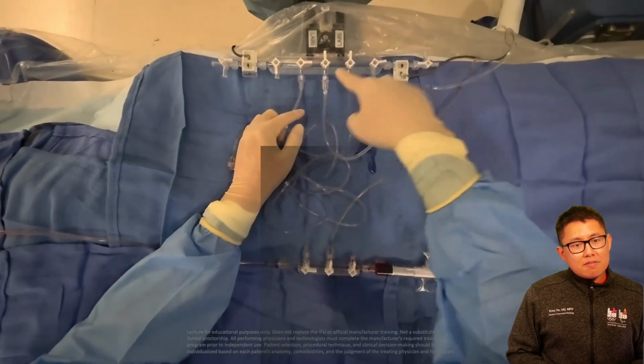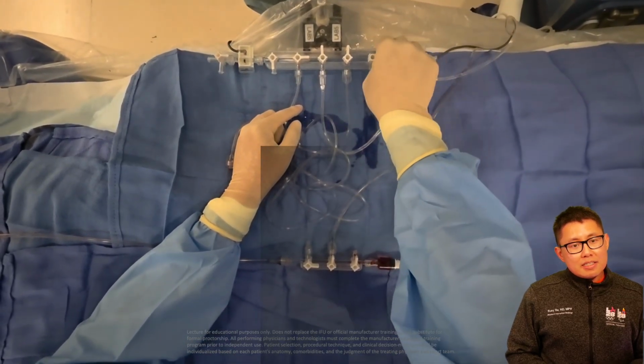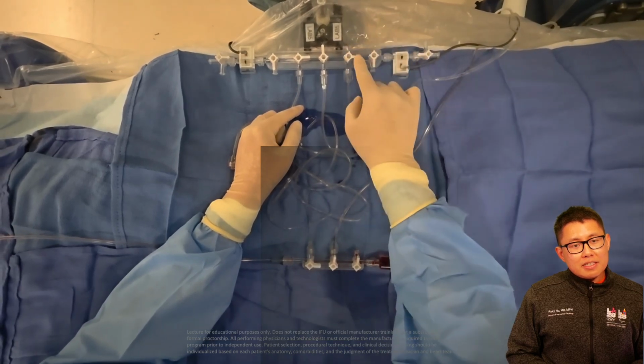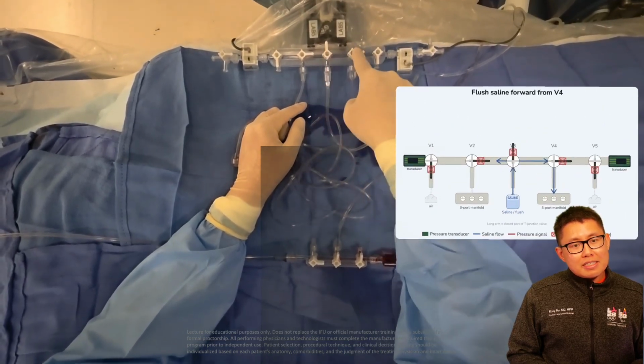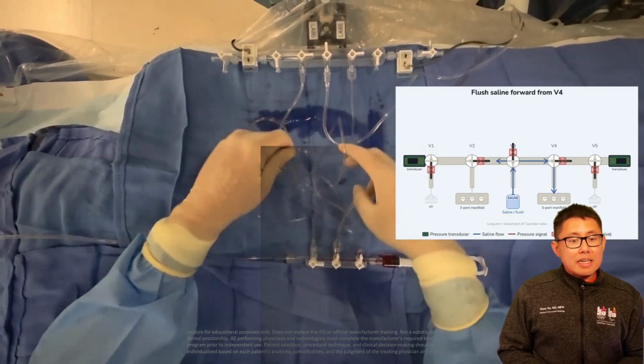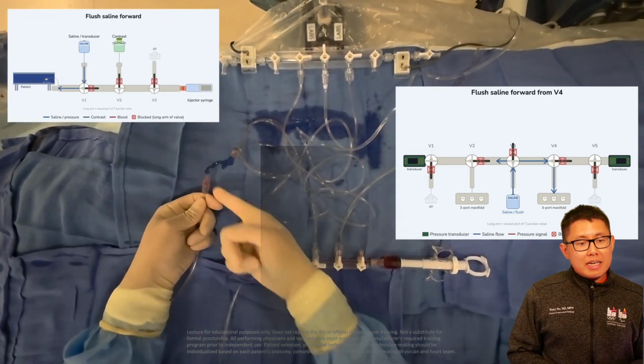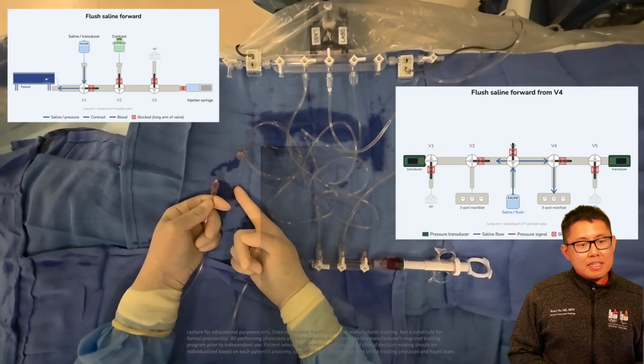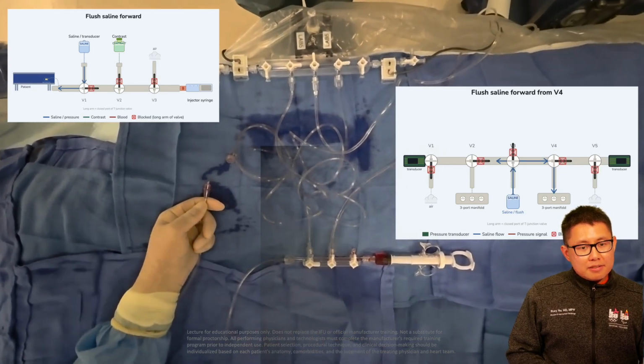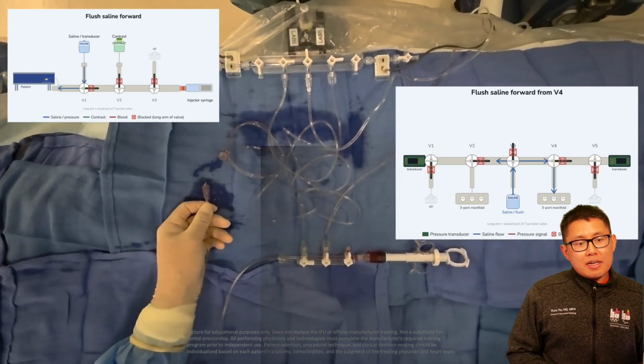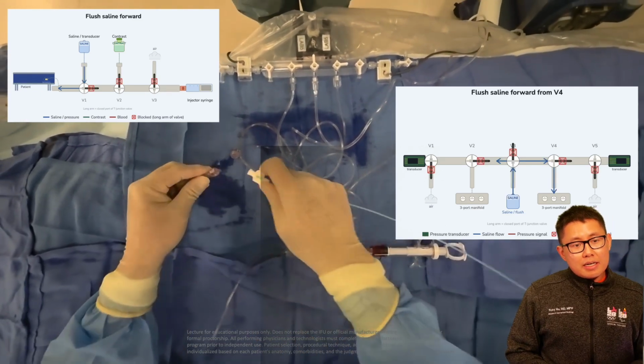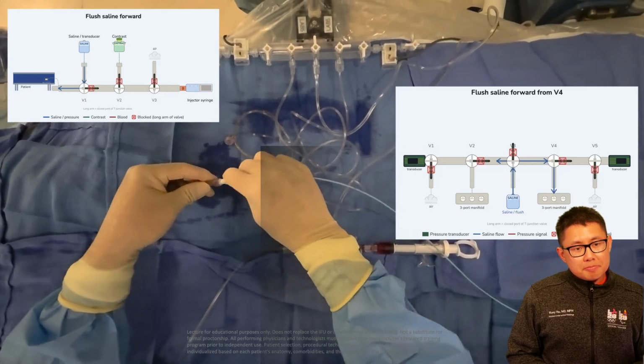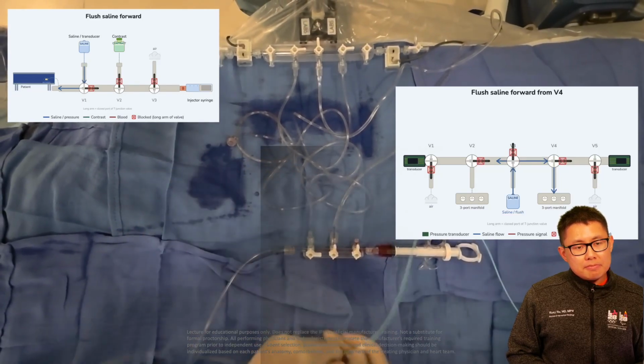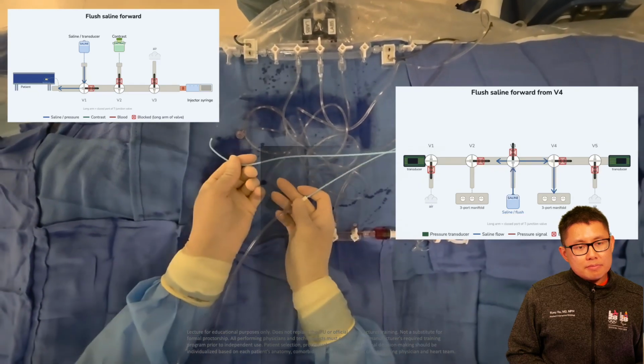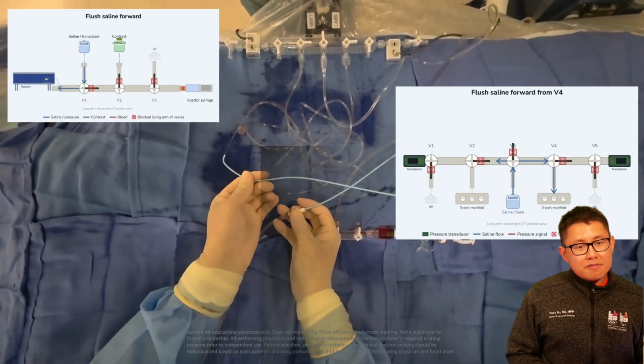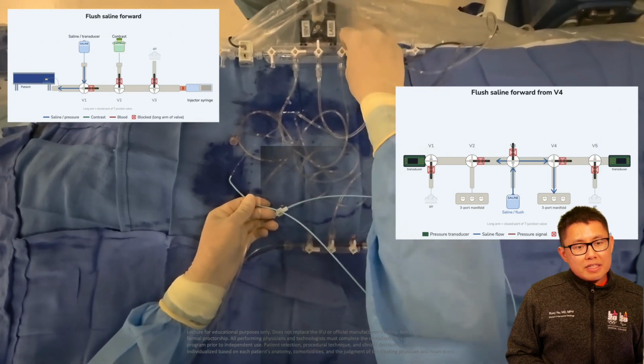So let's say we turn V4 up and we turn V5 to the right. The saline will just start dripping out of V5. Now let's close V4 to the right. Now the saline will follow this line that connects to our 3-port manifold, and it will come out over there in the flush saline forward mode. Let's study these two diagrams over here. This is something you want to do when you want to connect a catheter with a wet-to-wet connection. So you see now the saline is coming out from V4 to the 3-port manifold through the front of the catheter.